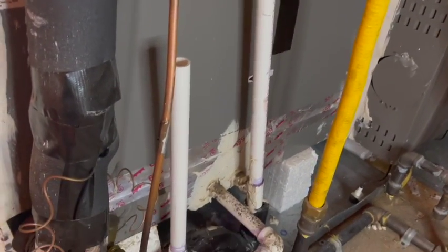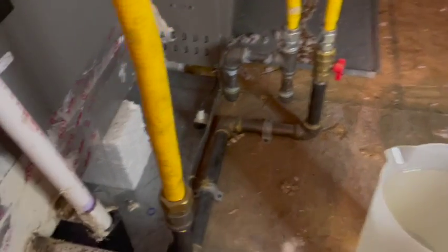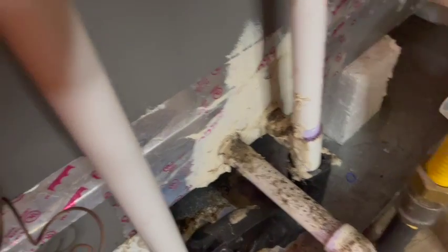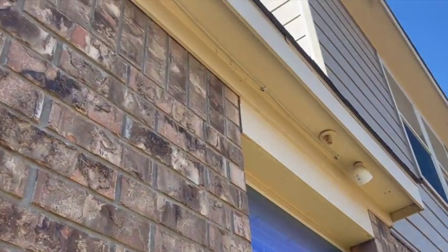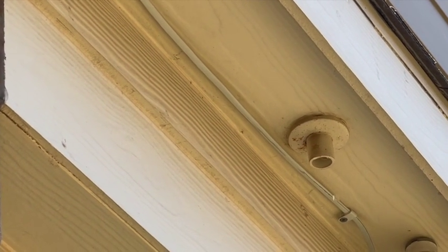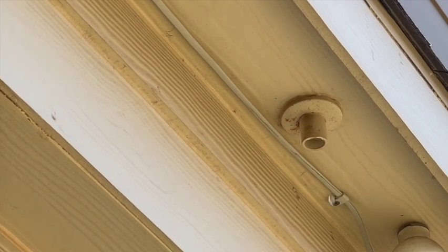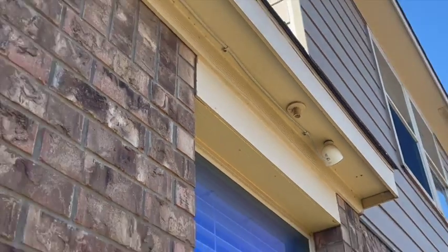I'm going to go ahead and flush the secondary line. All right, so now I've got the water for the secondary line. Let's go ahead and pour that into the pan, so it's level, and it'll start to drain out. So we want to make sure it gets to this point right here so it can drain out. Okay, I go out to the outside. I can see water dripping out of there. So that means the secondary condensation line is good and it's not clogged because it's allowing water to come through.